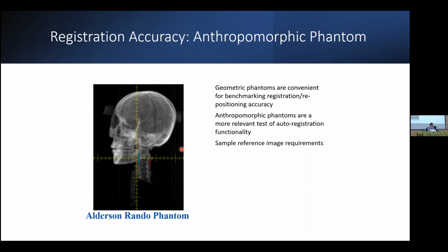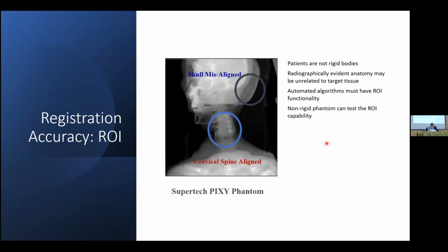So you can over process your thing and make it work really well for one particular thing and not something different. And as you know, if you're going to treat from basically head to toe, there are going to be all kinds of different anatomical sites you need to be able to test. So having a good phantom that you can test these different things with is important. Again, something you won't normally worry about with photons, but if it's a proton system where there are maybe only 2 or 3 of them that exist, and their IGRT is relatively new, it's important. So there are different phantoms, PIXY phantoms, different things, rigid bodies to test and make sure it picks things up. You can actually move them and do these things.